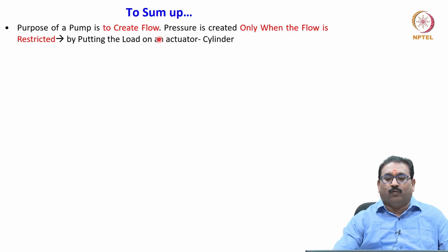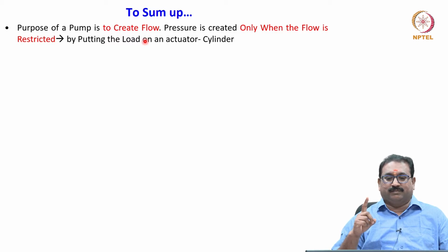To sum up on the pumps, the purpose of a pump is to create a flow. Note down, please, friends: pressure is created only when the flow is restricted. How? By putting the load on the actuator, either the cylinder or a motor. If there is no load, the pump will only eject the flow. That is why they are known as flow generators, not pressure generators.